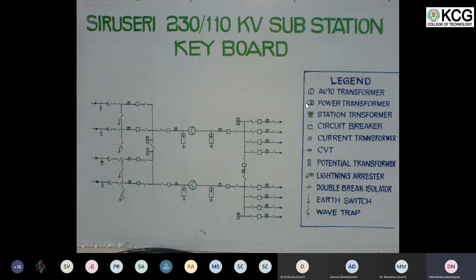We normally have the legend available in all the single line diagrams with the picture. So we can correlate this and we can identify 4 230 kV incoming lines with a 230 kV bus bar, 2 auto transformers, a 110 kV bus bar, and 8 outgoing feeders. So let's remember this single line diagram at least for the next half an hour, so that when we are moving on further, we will get a clear picture on what we are discussing. 4 230 kV incoming lines, 2 auto transformers, 230/110 kV, and 8 110 kV outgoing feeders.